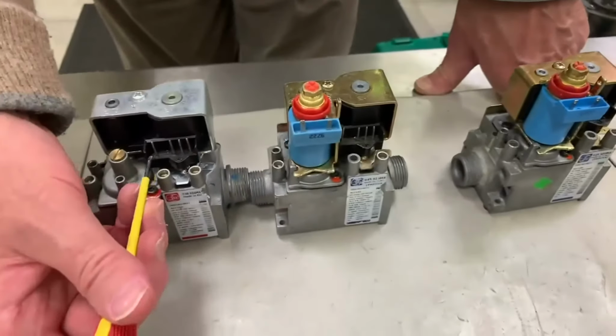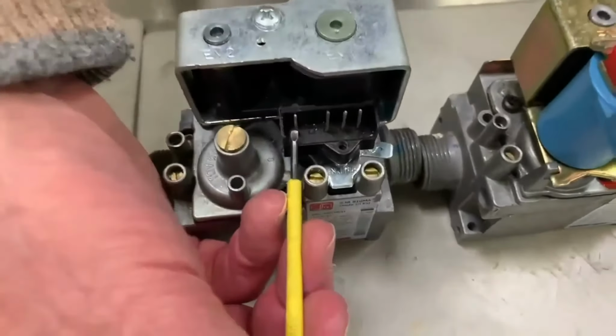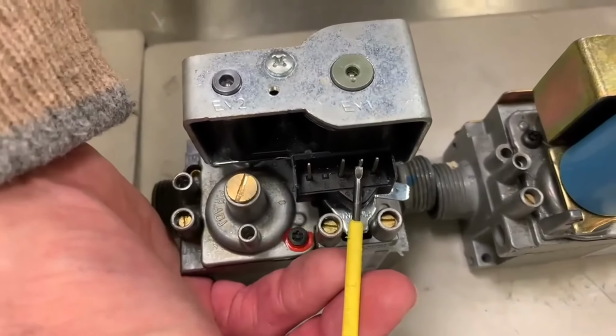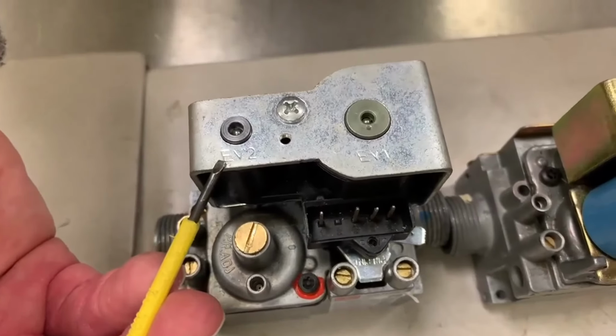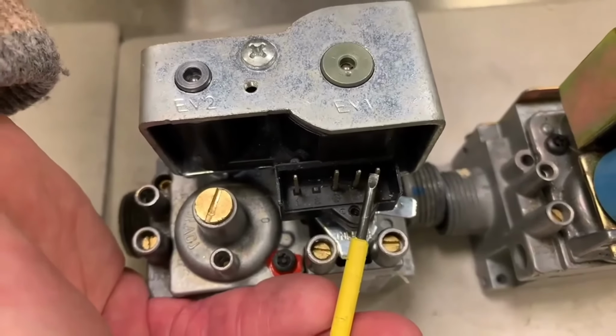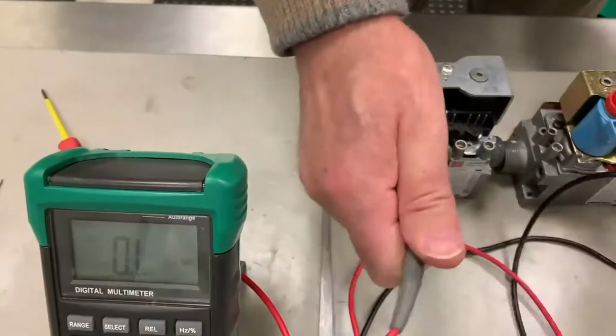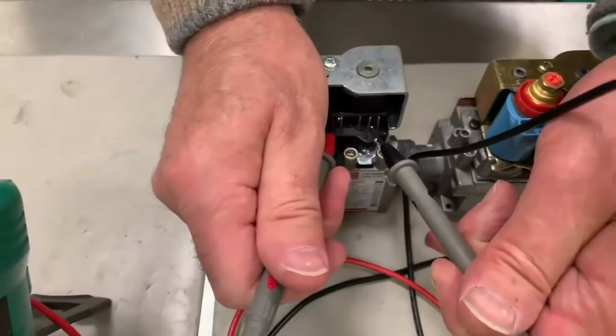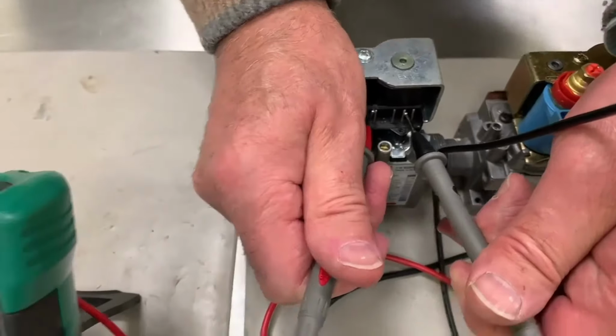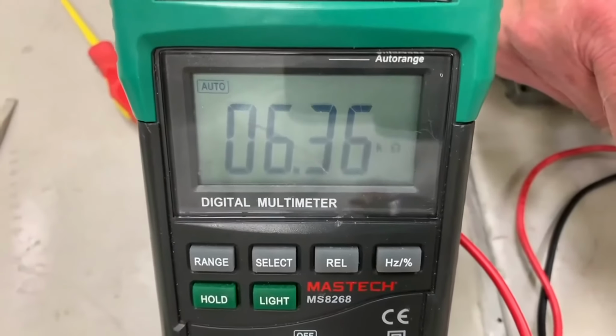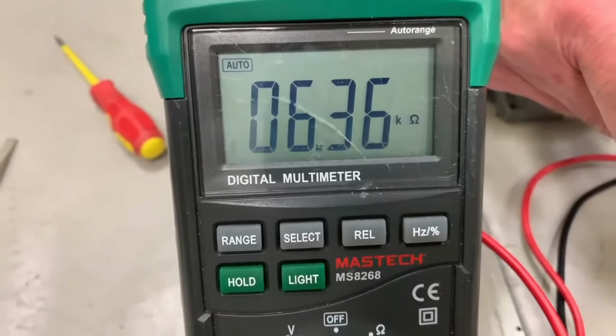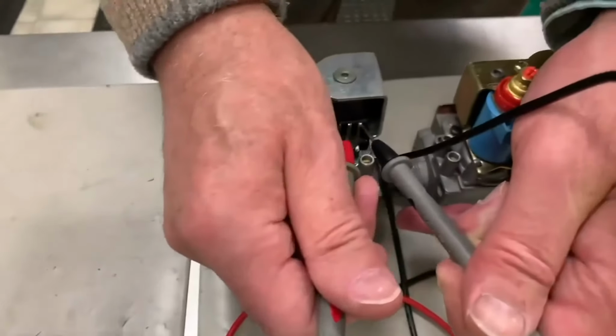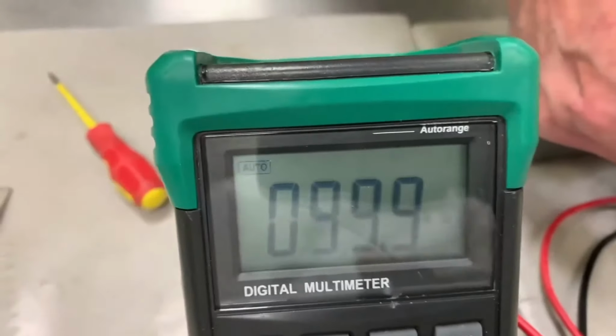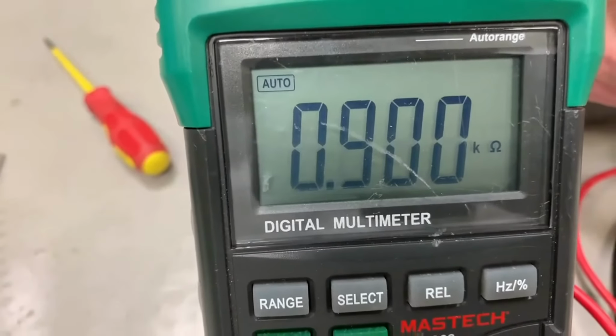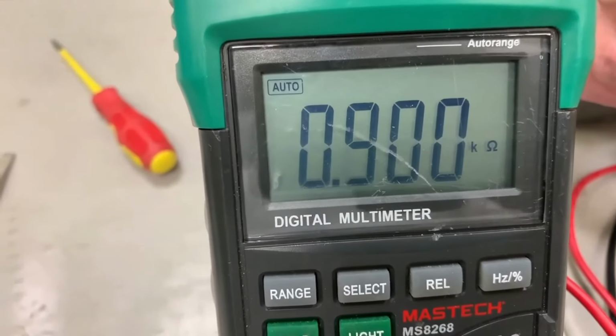These are 240 volt or 230 volt solenoids. To test, use the meter set for resistance. Pin 1 to pin 3 will test EV2. Pin 3 to pin 4 will test EV1. Pin 1 to pin 3 should give you about 6.4, there we are, 6.4 kilo ohms. So that's good. EV2 is okay. From pin 3 to pin 4, about 0.8 or 800 ohms, 0.8 of a kilo ohm. Well, that's 0.9, that's in the area, that's fine.